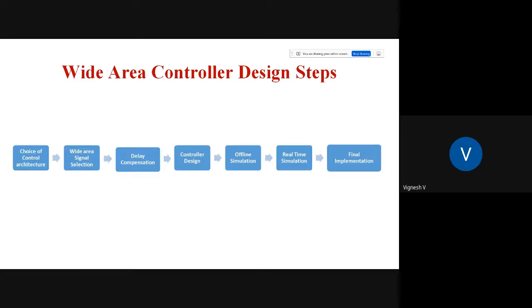When we design the wide area damping controller, we need to follow a few steps. First, the choice of control architecture, then we determine the right wide area signal in which the oscillations are visible. Because we're using a PMU from a geographically different location, there is practically a latency, and we have to compensate for this latency with delay compensation.